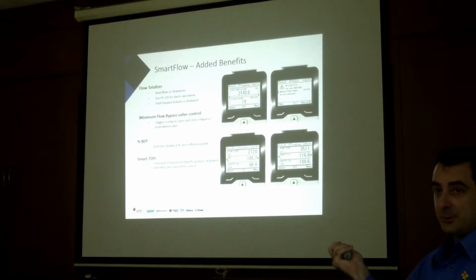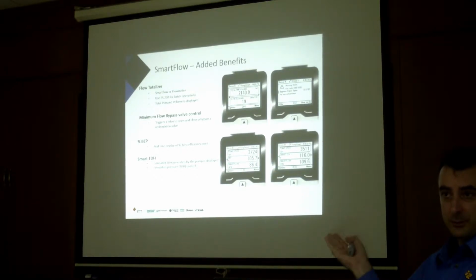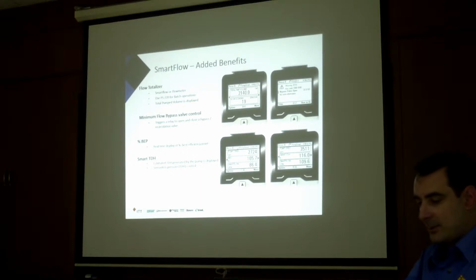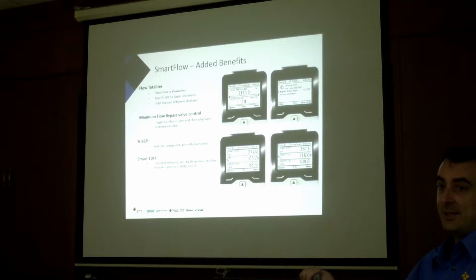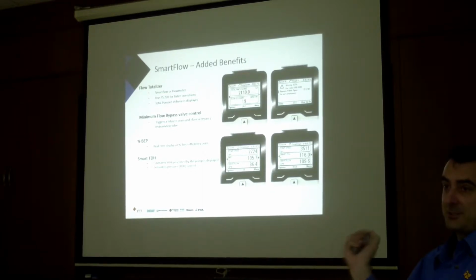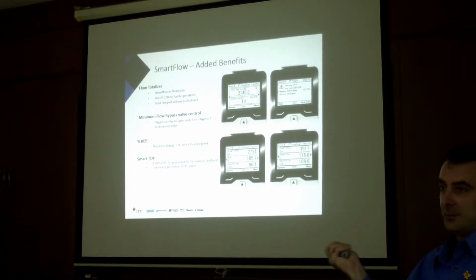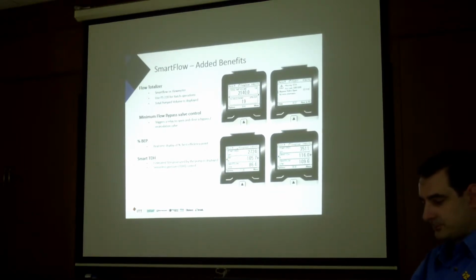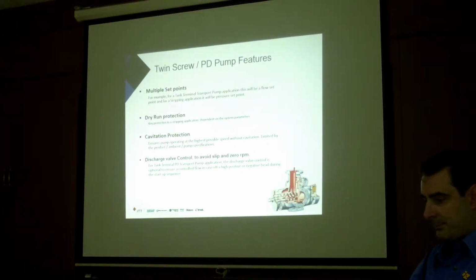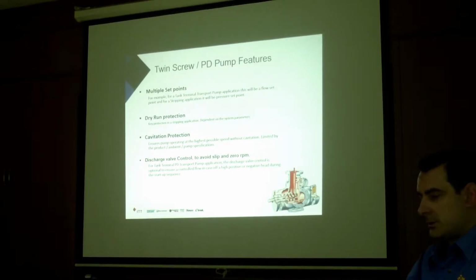It was difficult to do on these low voltage, but now we can because of the new technology. I'll show you how we use it. We also calculate head now, rather than just flow, so we can tell the head. Actually, in the next software version, we will be able to control pressure without a pressure transmitter, or head without a head pressure transmitter. So that's going to be good for some applications. Twin screw and PD pumps, we do a few features. They're more custom applications.